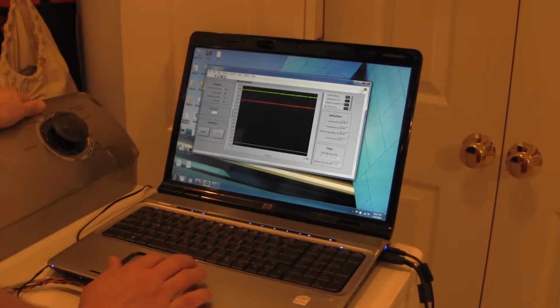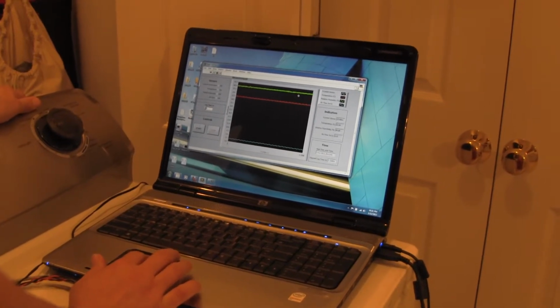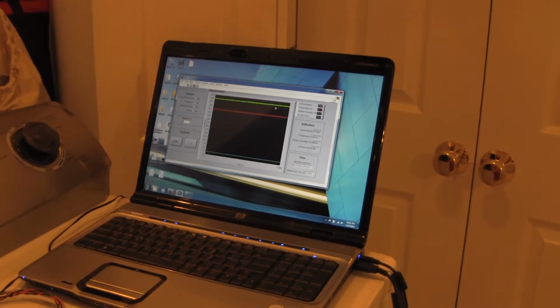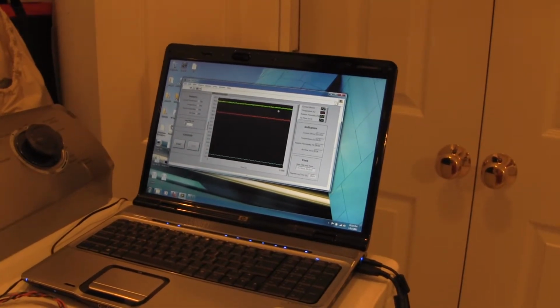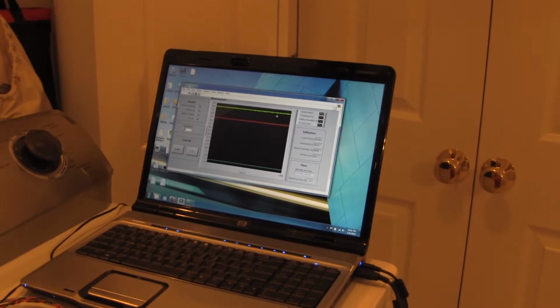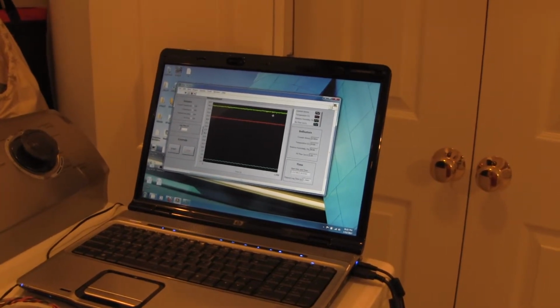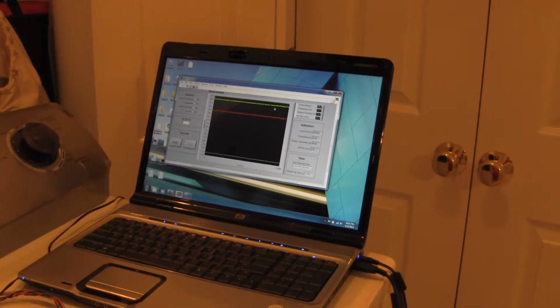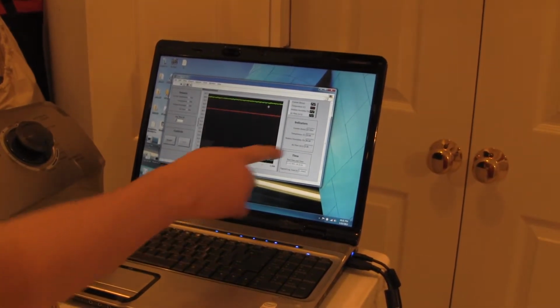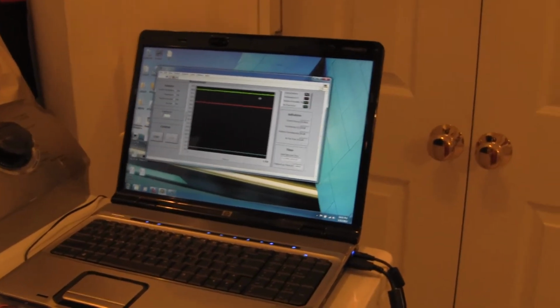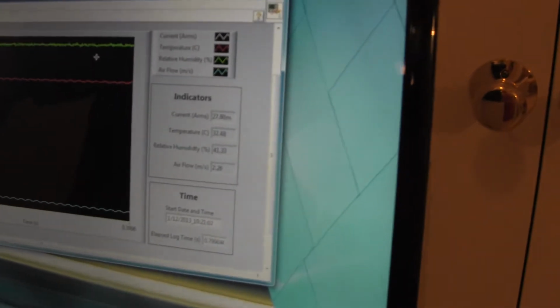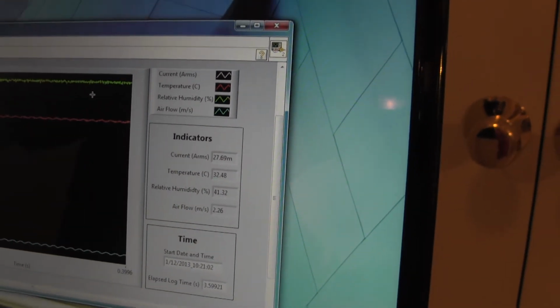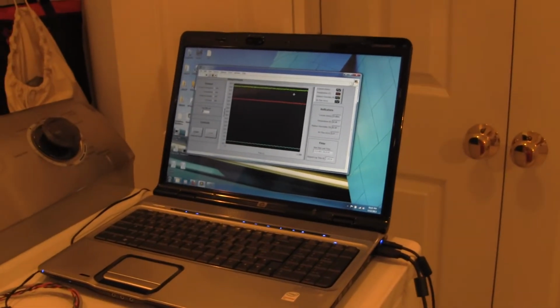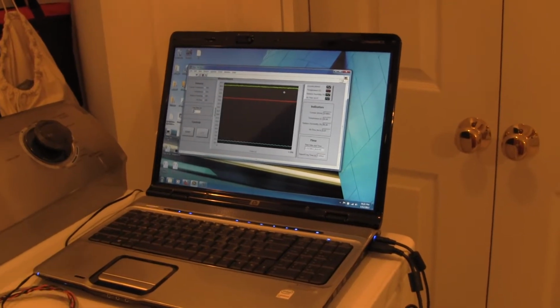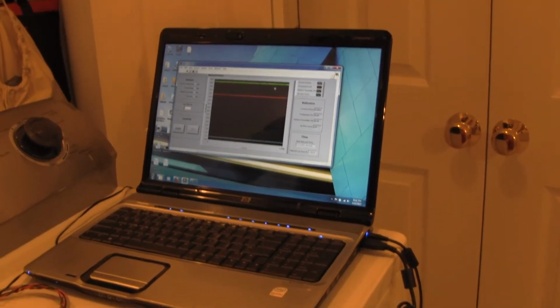If you notice, the relative humidity's 40%. It's pretty hot in here because I've been running this dryer without the exhaust on it. That's just the easier way to access it, to take the ductwork off the back there. So what we'll do now, if you notice, the current is 27 milliamps, so it's nothing pretty much. Temperature right now, like I said, it's hot in here, so it's about 32 C. Relative humidity is around 40%, and the airflow is nothing because it's not running.